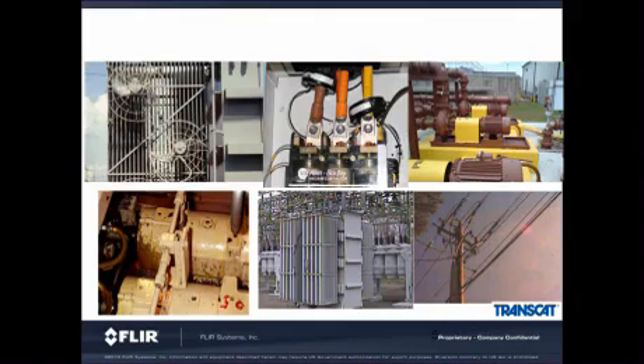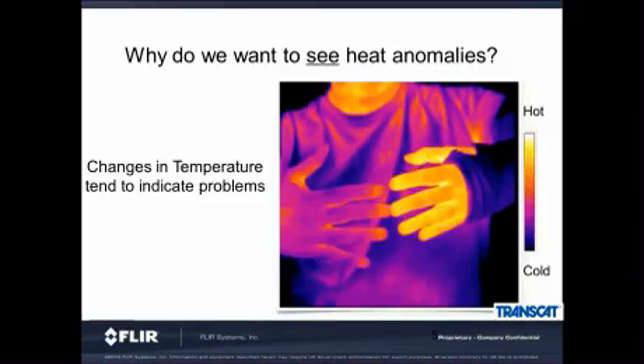Every day you walk around your work environment wondering when the next problem will happen or what will fail next. Without the proper tools, it's impossible to detect these pending problems. Generally, our human senses are unable to detect the clues to these potential failures. However, industrial equipment does give off one major clue. When equipment goes bad, it generally heats up. Mechanically, because of friction. Electrically, because of resistance. All these targets get hot prior to failure. And wouldn't it be nice to see that? A change in temperature or a difference between two similar components can show a problem.